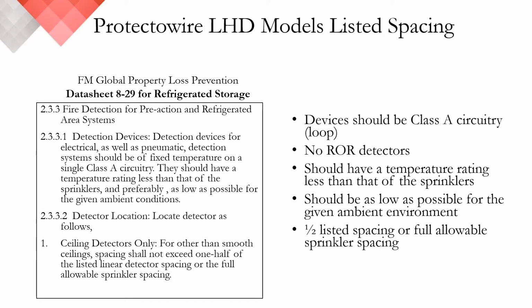For all refrigerated and freezer warehouses, FM requires Class A loop circuitry to assure there is detector redundancy in case of a break. Rate of rise detectors are not acceptable because of false alarms due to doors being opened or other abrupt localized temperature changes. The detector should have a lower temperature rating than the sprinkler heads used within the facility, and ideally as low an activation temperature as possible given the ambient conditions.